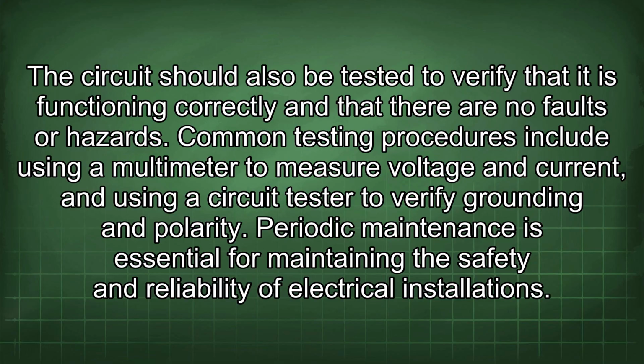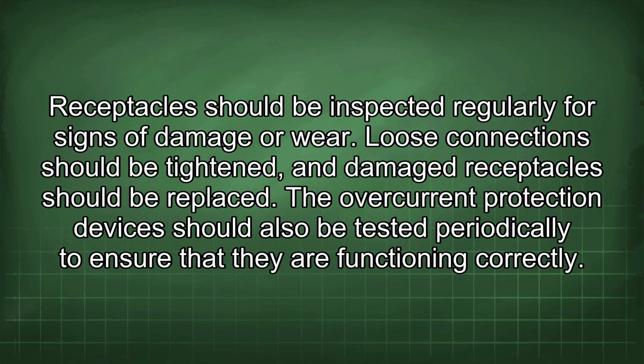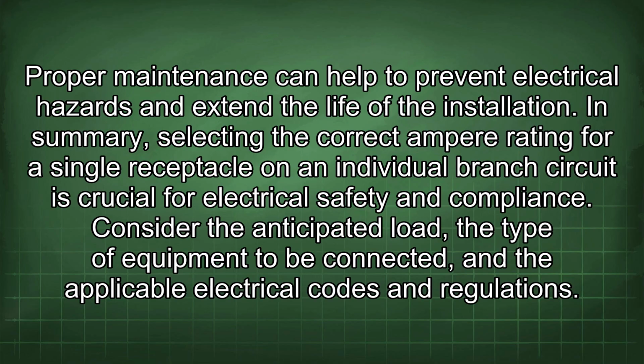Common testing procedures include using a multimeter to measure voltage and current, and using a circuit tester to verify grounding and polarity. Periodic maintenance is essential for maintaining the safety and reliability of electrical installations. Receptacles should be inspected regularly for signs of damage or wear. Loose connections should be tightened, and damaged receptacles should be replaced. The overcurrent protection devices should also be tested periodically to ensure that they are functioning correctly. Proper maintenance can help to prevent electrical hazards and extend the life of the installation.